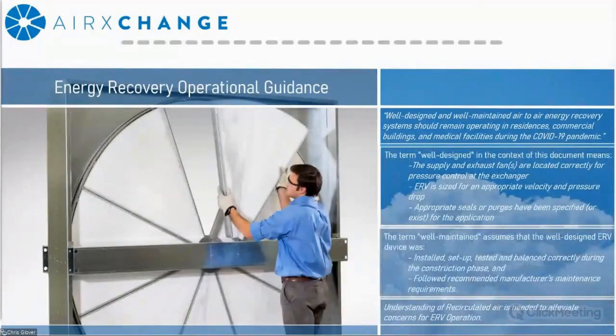Okay, so as we discussed the operational guidance for the ventilation system, what if your system is equipped with an energy recovery device? So here's some guidance as it relates to energy recovery. Well, first and foremost, a well-designed and well-maintained air-to-air energy recovery system should remain in operation. Now, you may be asking yourself, what does well-designed and well-maintained mean?